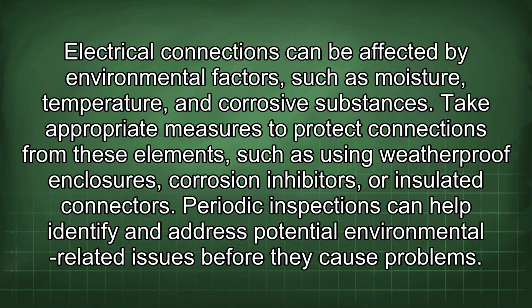Electrical connections can be affected by environmental factors such as moisture, temperature, and corrosive substances. Take appropriate measures to protect connections from these elements, such as using weatherproof enclosures, corrosion inhibitors, or insulated connectors. Periodic inspections can help identify and address potential environmental-related issues before they cause problems.